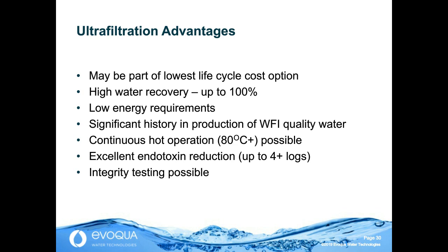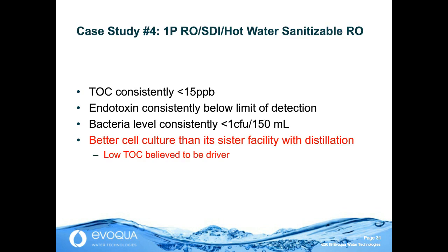and active ingredient production. The last case study now goes back to the days when USP only allowed distillation or reverse osmosis as the final process. This is why this got configured. And the final TOC was consistently below 15 ppb, with endotoxin and micro at very low levels. And there was a sister facility with a distillation system. In this facility they opted to put in RO, and the cell culture in this facility was better, which they attributed, they believed, to the lower total organic carbon for membrane made for better cell culture in the facility.